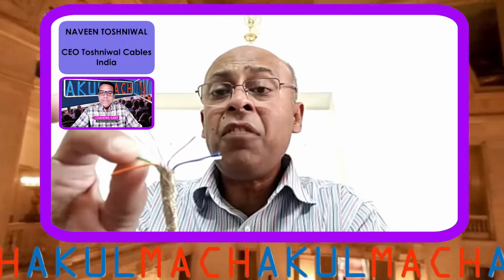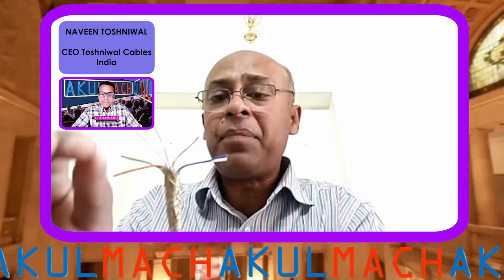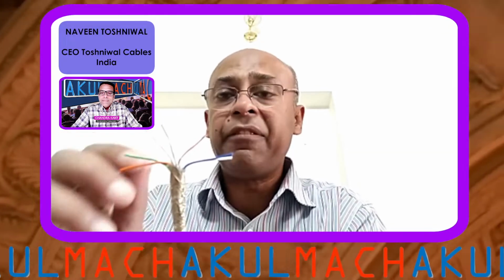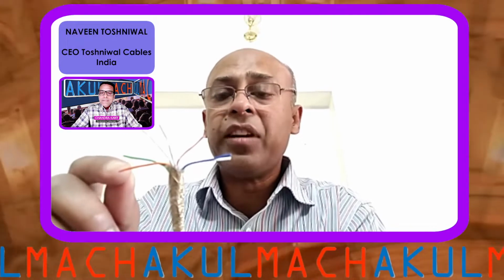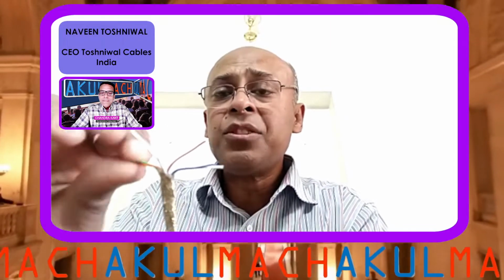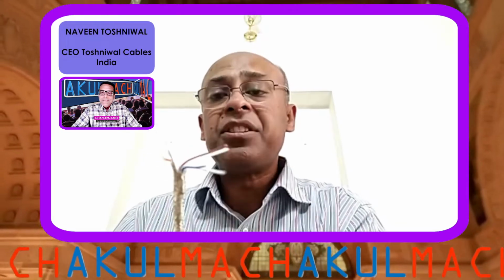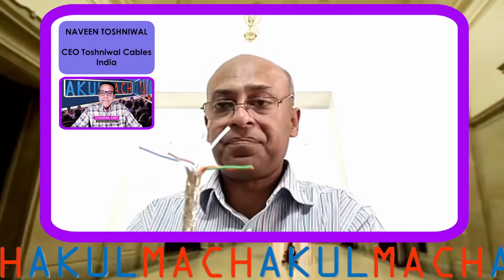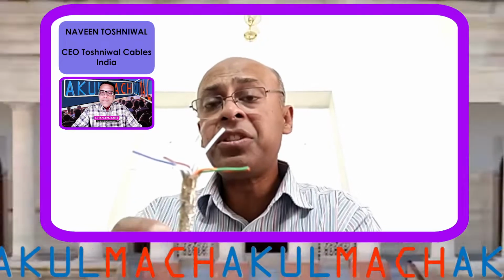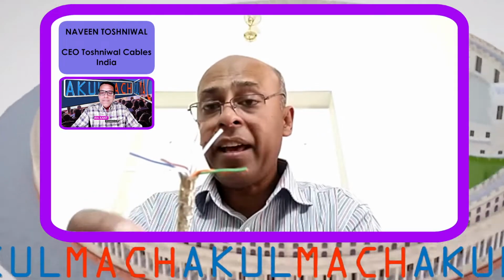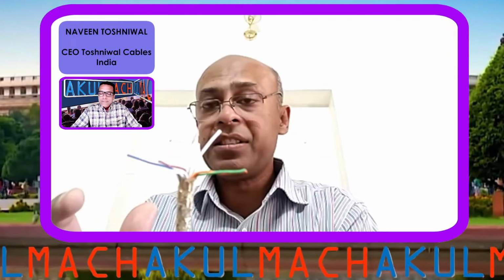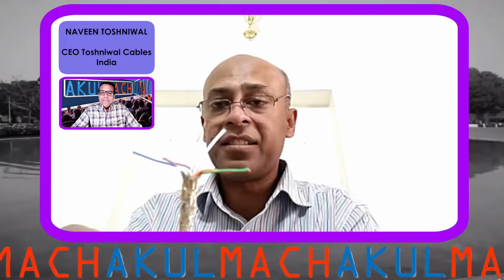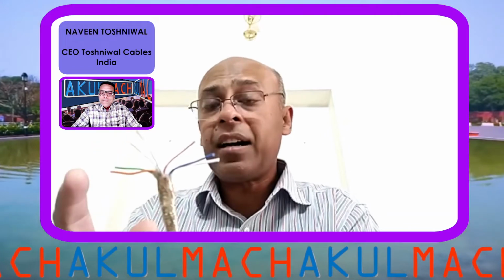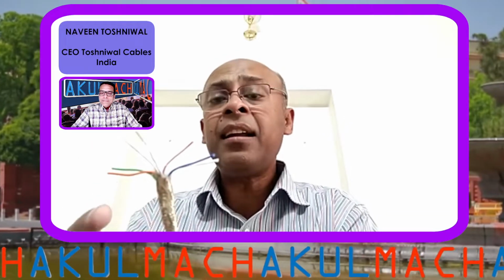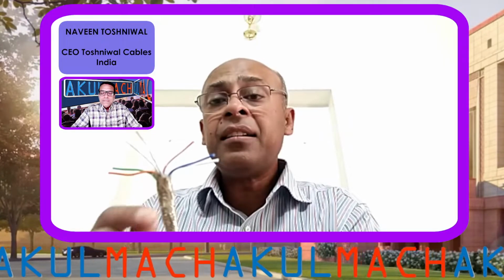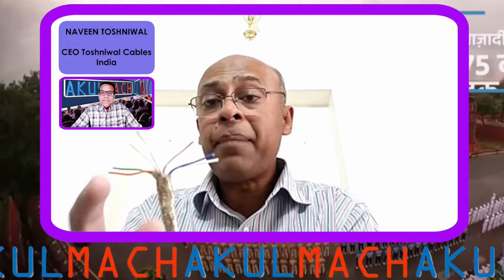This is of Teflon. Teflon is basically a brand name. The chemical name of the insulation is PTFE, polytetrafluoroethylene. This insulation can withstand a temperature of 260 degrees continuous operation. So this cable can be used in areas where there is a high temperature continuously, like in the range of boilers or furnaces. Plus, Teflon has other very important properties: it is moisture resistant and also chemical resistant.